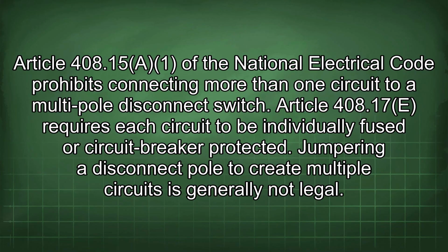Article 408.15a of the National Electrical Code prohibits connecting more than one circuit to a multi-pole disconnect switch. Article 408.17e requires each circuit to be individually fused or circuit breaker protected. Jumpering a disconnect pole to create multiple circuits is generally not legal.